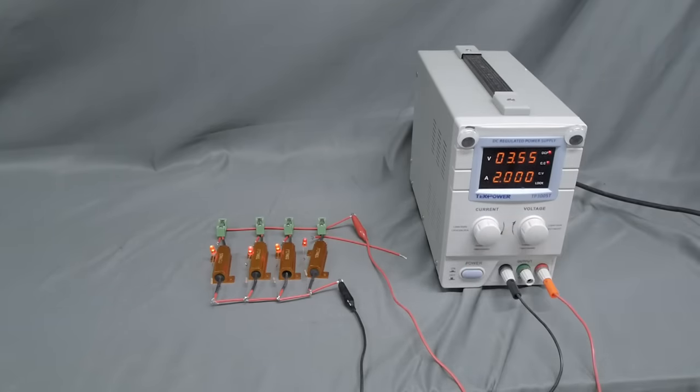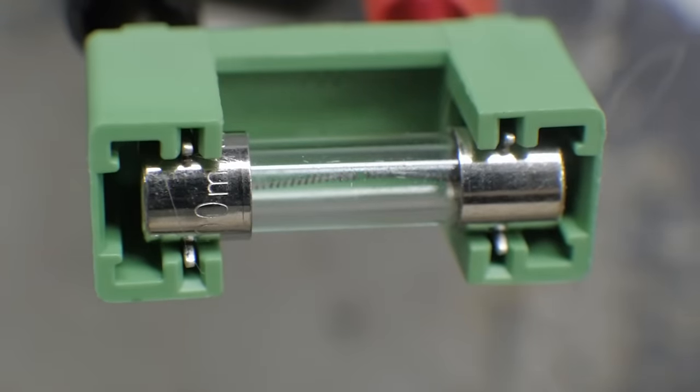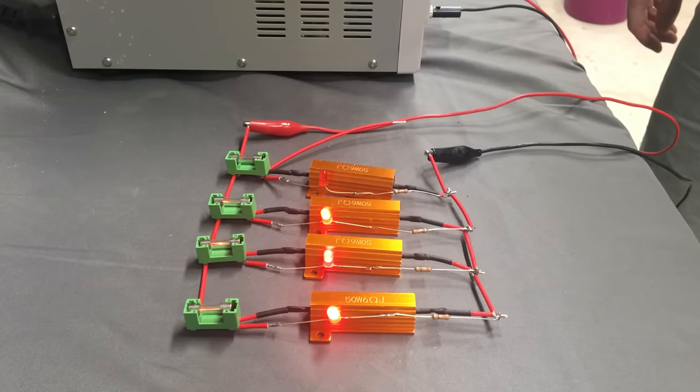But there are cases when isolation of equipment can actually make things worse, and I built a little demo to show how this works. Imagine a series of interconnected transmission lines, all feeding their own service areas, represented by the power resistor and LED light in this model. During peak demand, these lines might be operating at nearly their maximum capacity. If one line experiences a fault — for example shorting out against a tree branch — protective relays will isolate the line; in my demo, the fuse blows. But if not handled correctly, the entire electrical load gets automatically distributed between the remaining transmission lines, pushing them beyond their limit. All of a sudden you have a cascading failure. Much of our grid is designed to avoid this, but occasionally the perfect alignment of faults, communication errors, and human factors leads to massive outages — like the one in 2003 that took out much of the US Northeast and Ontario.